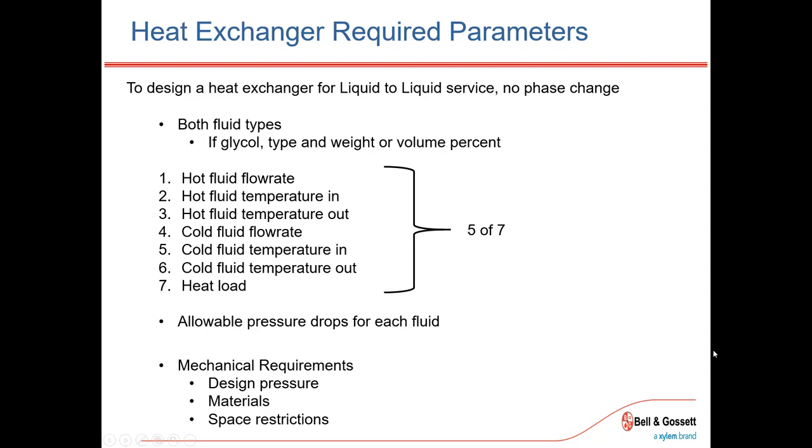A big point to pay attention to, though, would be pressure drop of each fluid. And one of the tips that we've got towards the end is just confirming on the schedule that the pressure drop is clearly defined, and that when people submit on units, that it's clearly defined. It's quite common that people will confuse feet of head with PSI, which will give completely different results. And we'll show the impact of how you can increase your heat transfer rate by allowing for a higher pressure drop, but then also by allowing a higher pressure drop, you're accepting more power consumption, or a loss over time. Try to go to the next one.